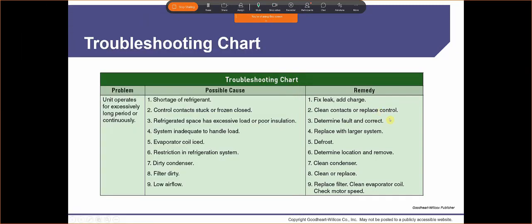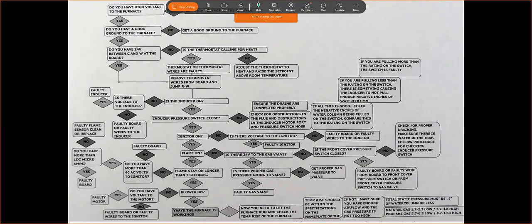Let's just say the inducer motor is running, we hear a little click coming from the board, but our hot surface igniter never turns orange. Well then, I may have an issue with that hot surface igniter. Maybe it's broken, and I need to replace it. So knowing my sequence of operation helps me determine what next step I need to make. All right, my hot surface igniter turns orange, but I get no gas. Well then, I may have an issue with the gas valve, or I may have an issue with the board. So, all different things you guys will learn.